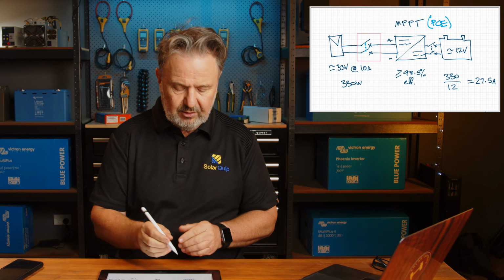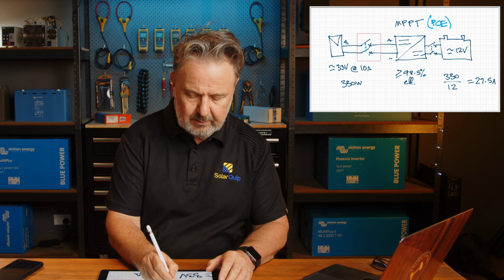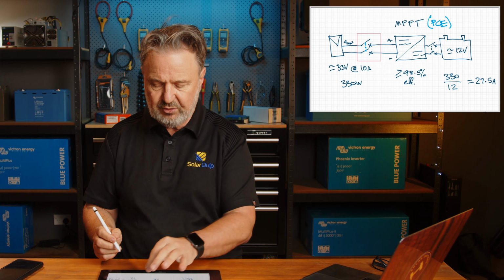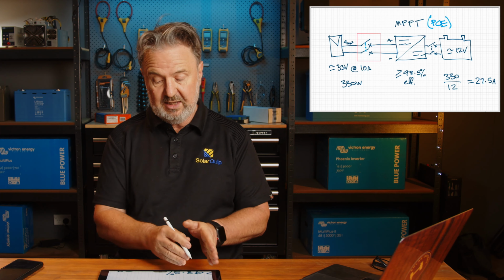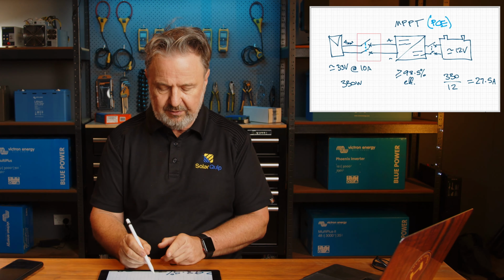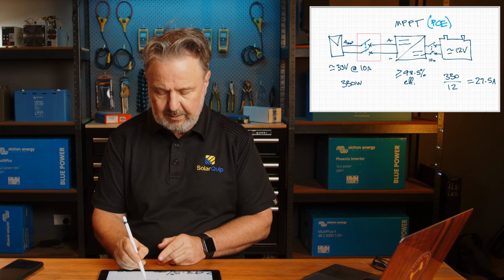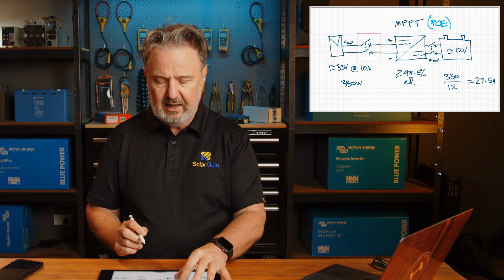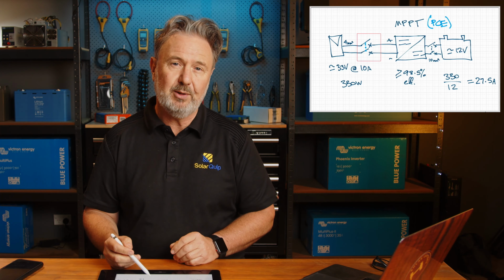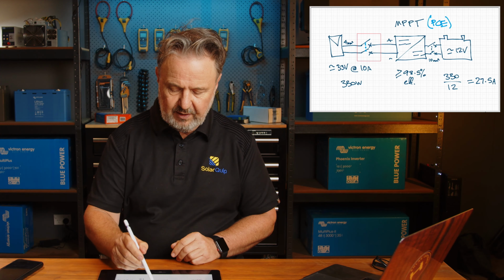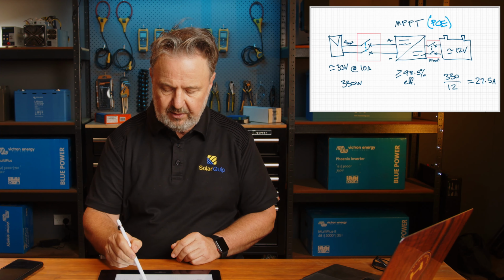The reason that we've got two is it's likely that there's a gauge change between the battery cable size and the PV array cable size. Typically, on smaller systems, PV array cables are quite small, not uncommonly something like 4mm square cable, which is pretty popular for PV arrays in Australia. But your battery cable might be determined by higher current, so a larger cable size. Let's say you've got 10mm square cable going to your battery to allow for higher current flows. That means the protection for that cable needs to be sized appropriately so that you can pass through the maximum current, but it's protecting that 10mm cable from thermal overload. So there are your two points of isolation and overcurrent protection on that design.